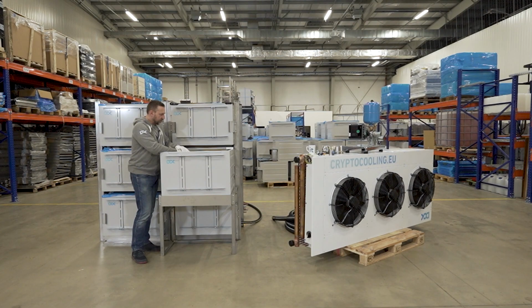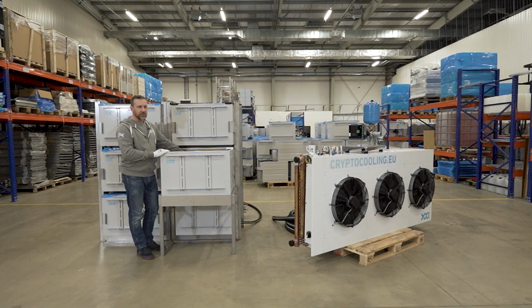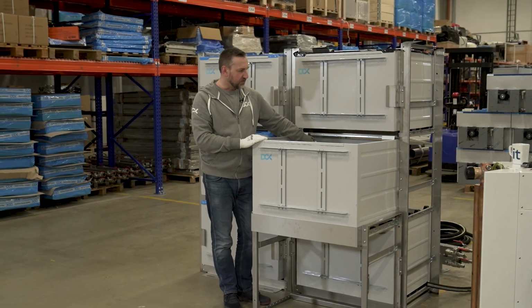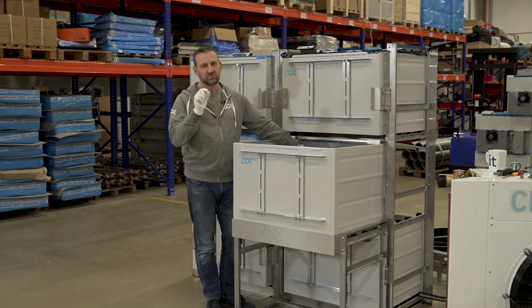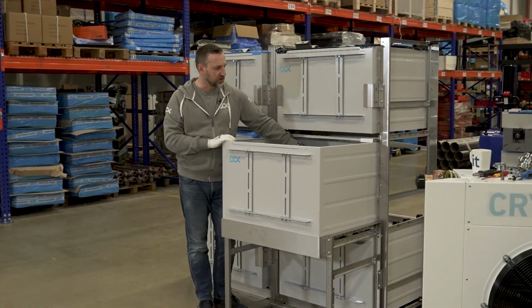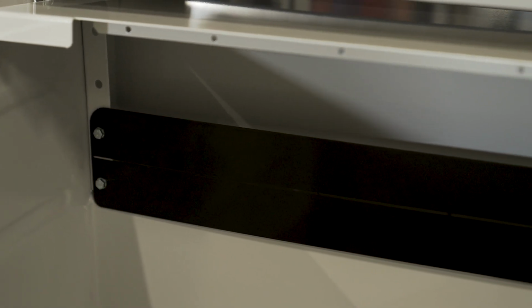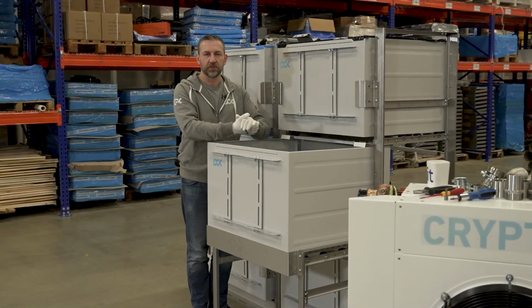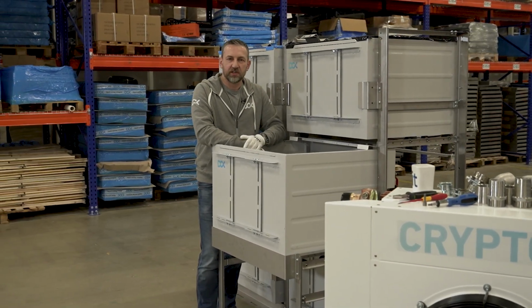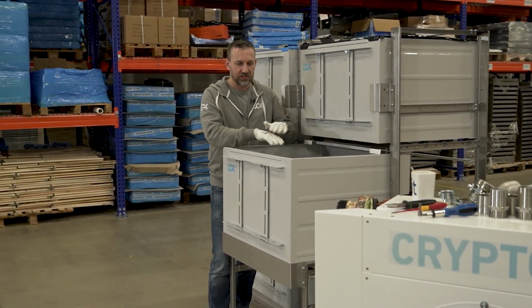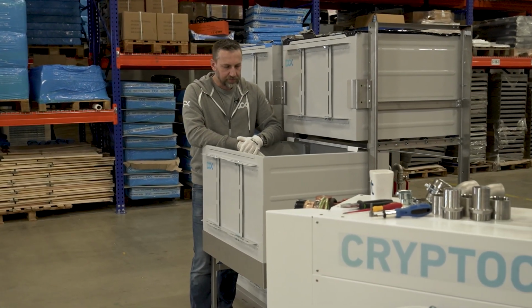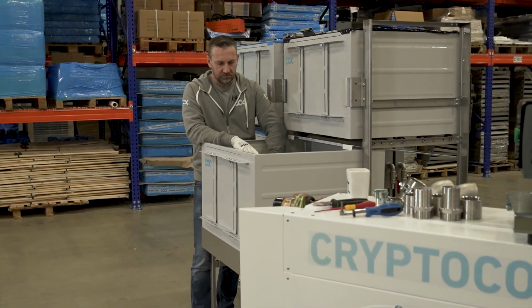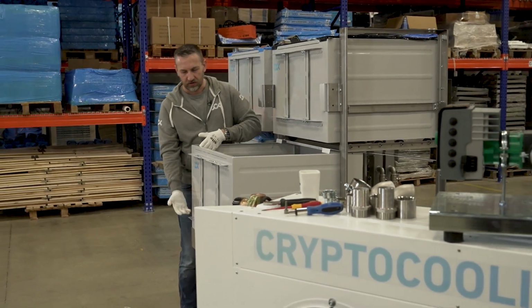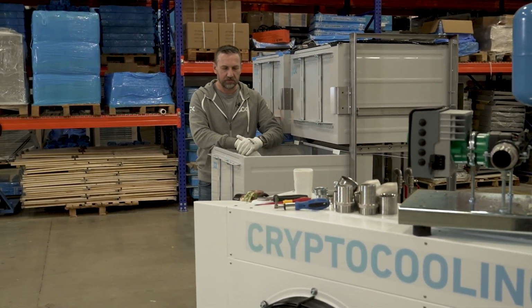The only final thing you need to do when starting your enclosure is the fluid level inside. It should be just 1 millimeter above the divider plate inside the enclosure, just to make sure there's a nice waterfall, since the hottest part of the fluid stratifies inside the enclosure and is pumped, but there are still different temperatures depending on the height of the fluid.